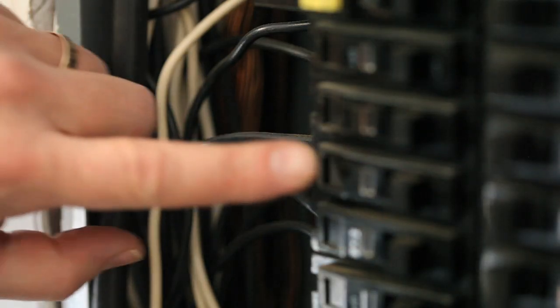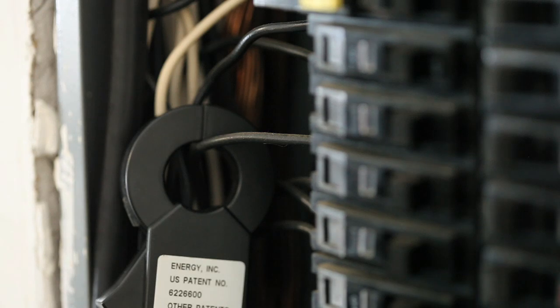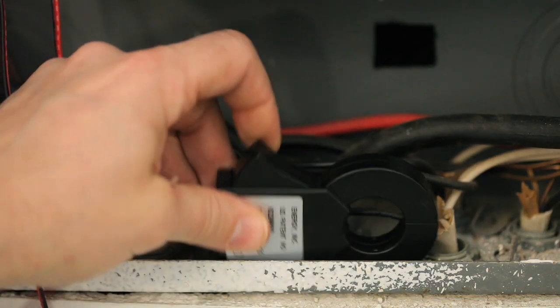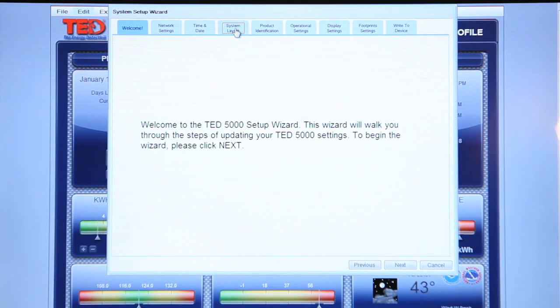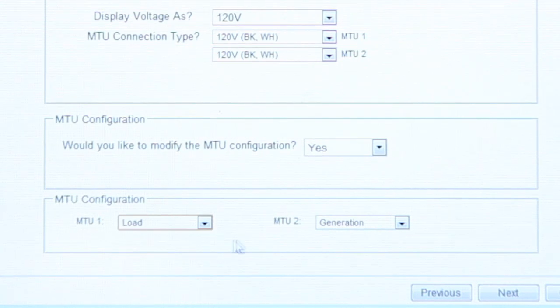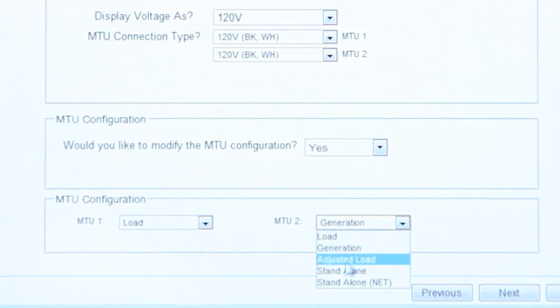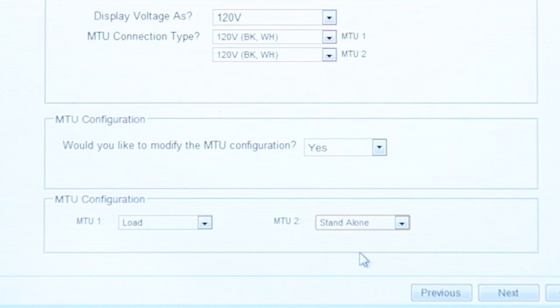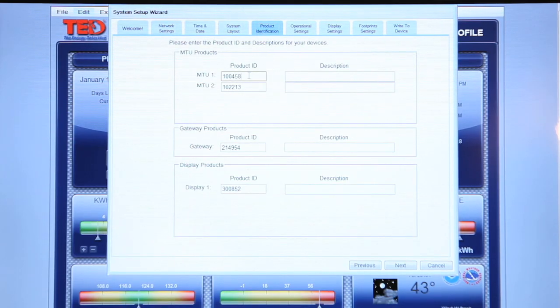Next, we can try monitoring an individual breaker. Simply connect one current transformer to the breaker that you'd like to measure. Keep in mind that the MTU will measure the net of both current transformers, so in this case one current transformer will not be used. On our Footprints software, we will change the first MTU to load and the second MTU, which is monitoring the individual breaker, to stand-alone. This will show us the reading of the breaker without adding the measurement to our net reading. While entering in both MTU serial codes, make sure they correspond to the correct measurement.